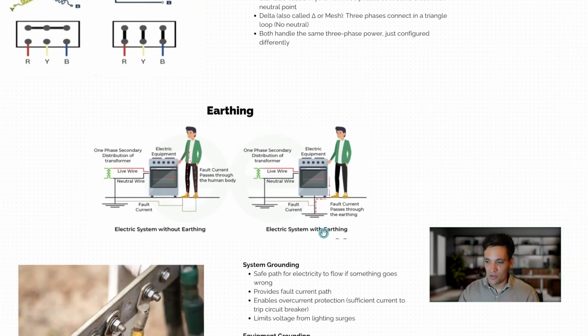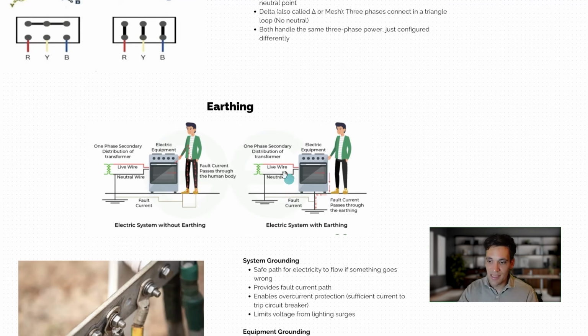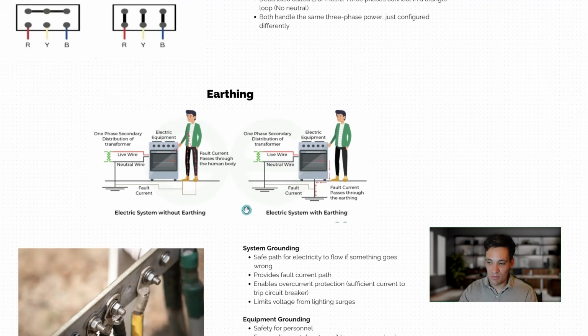Now, what does earthing do? So earthing ensures that if there's any fault on the system, all of the metallic components of the system are bonded to ground. So because there's this earth here, now when the live wire touches the frame of the equipment, the fault current will pass through to ground, which ensures that if you touch it, you might get some sort of shock, but you won't get nearly the same amount of shock, as the lowest resistance path to ground is through the earth connected to the equipment. This will also ensure that the circuit breaker that's protecting the system will trip because the fault current will be significant enough to trip the breaker. Without it, in this situation, if you've got an overcurrent protection on the circuit, because there's actually no path to ground until someone touches the device, the circuit breaker won't trip.